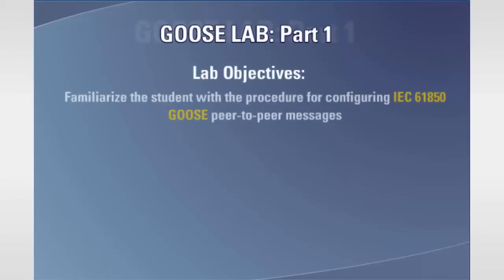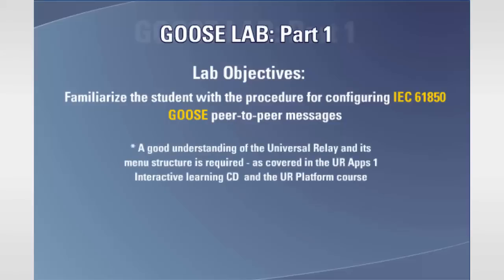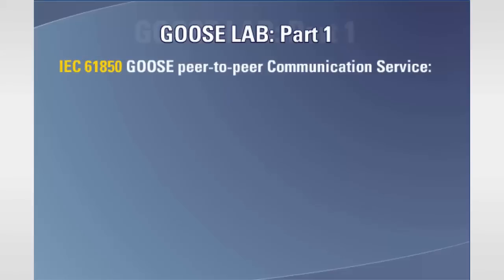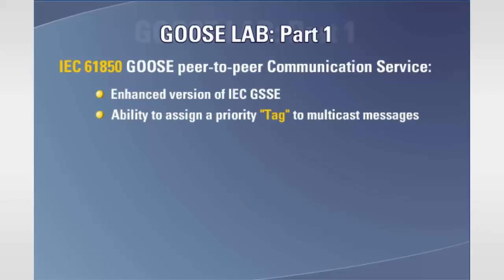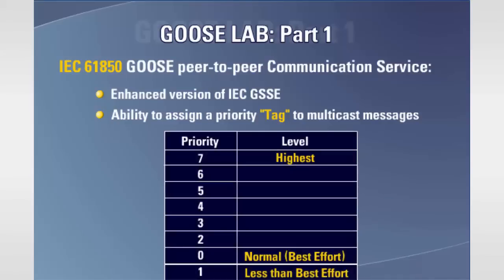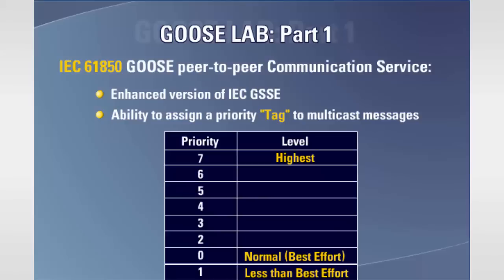The objective of this lab is to become familiar with the correct procedure for configuring the IEC 61850 GOOSE peer-to-peer messaging service. The IEC 61850 GOOSE peer-to-peer communication service is an enhanced version of the GSSE peer-to-peer service with the additional ability of assigning priority and what is called a tag to the multicast messages. The priority can range from 0 to 7. A priority value of 1 is the lowest level of priority. A priority value of 0 indicates the default priority, also referred to as best effort. Best effort has a higher priority than 1 and a lower priority than 2. The level of message priority increases as the value is increased from 2 to 7, with 7 being the highest priority.